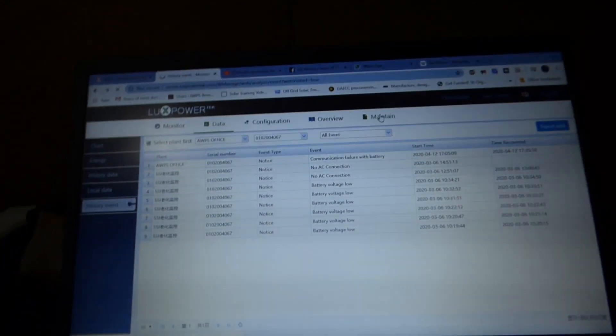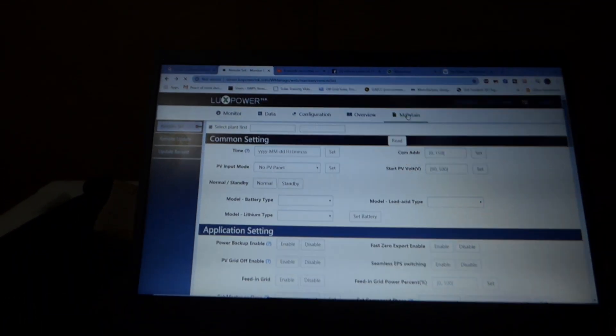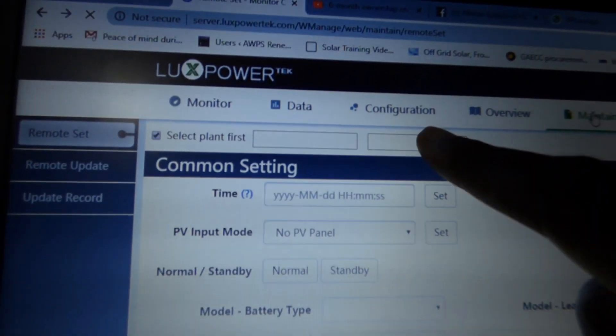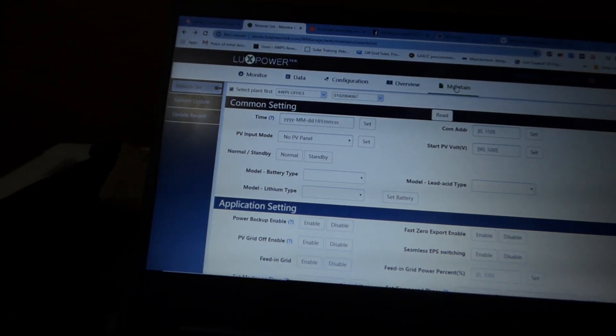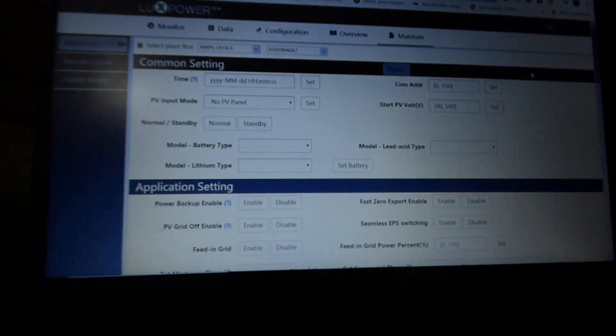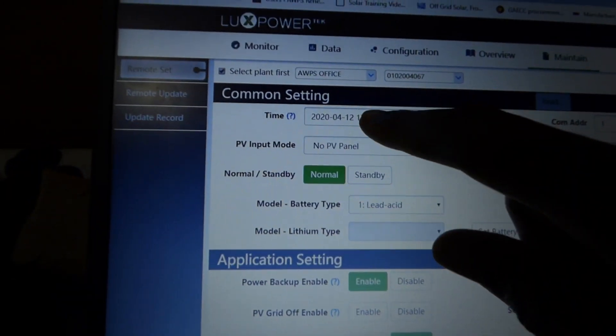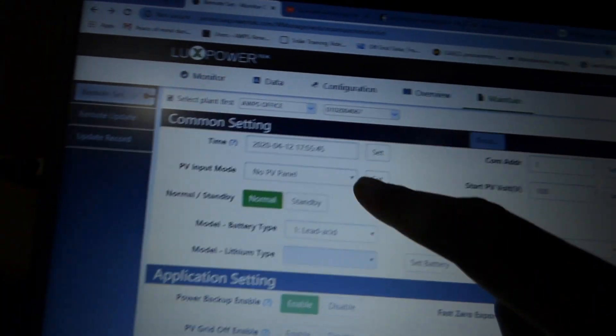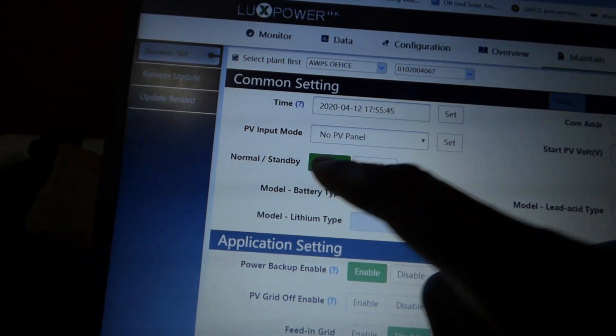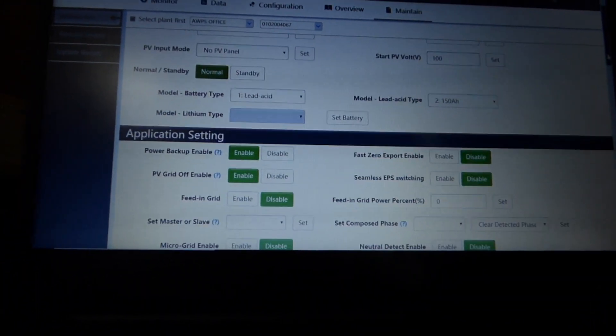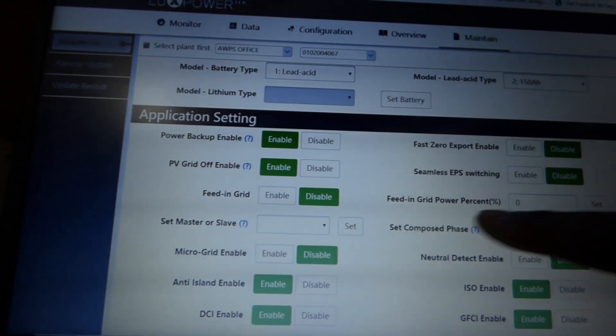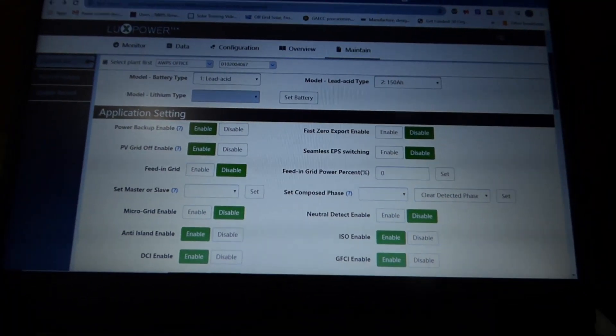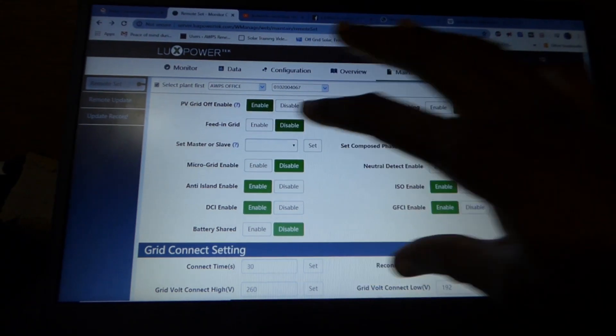So this is where you program the inverter, where you change the settings, where you change the parameters. Once this loads, it's going to show you your plant. And then it's going to show you the serial number of the plant, which is—they call the inverter plants. I guess it's a solar plant. So it's showing that. And then you click on read. And then it's going to try and read the inverter in real time. And then it'll show you what settings are on. So for example, right now, this is the time. We're using comport one start voltage of a hundred. I could change that to zero because there's no PV input, no PV panels. It's on normal mode. My battery type is lead acid, and I selected 150 amp hours. And then here, as you could see, power backup is enabled. PV grid off is enabled. Feed in is disabled.